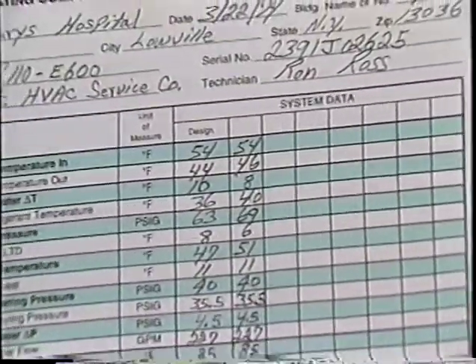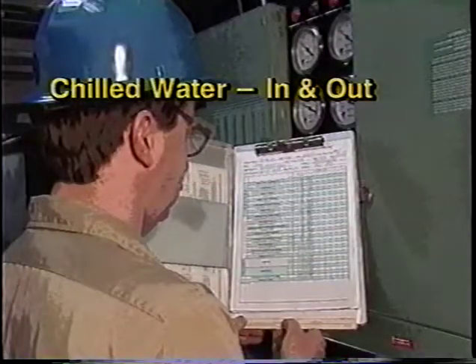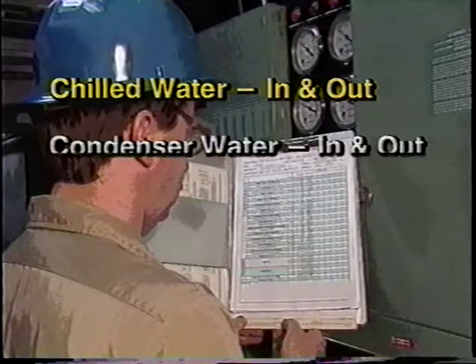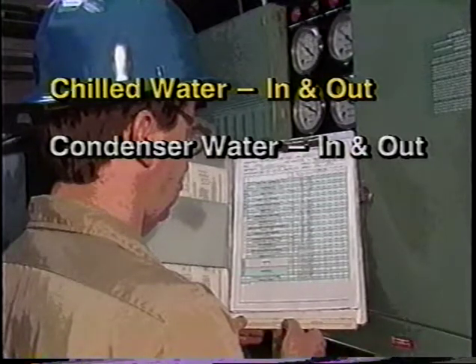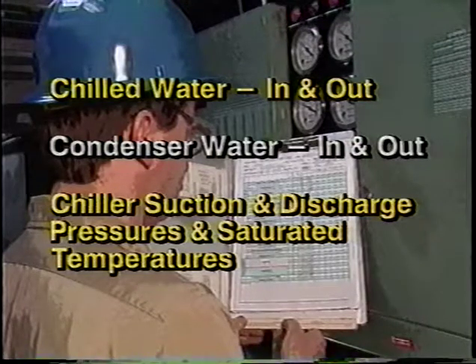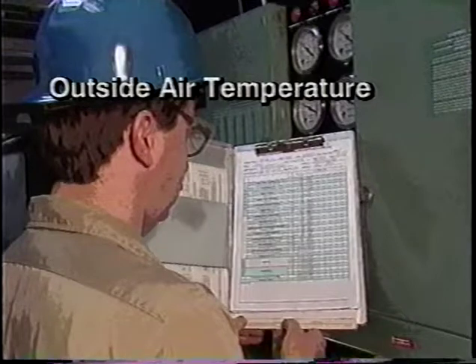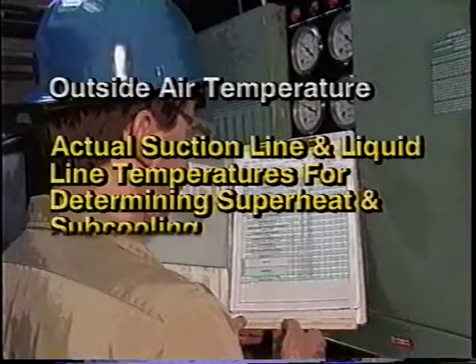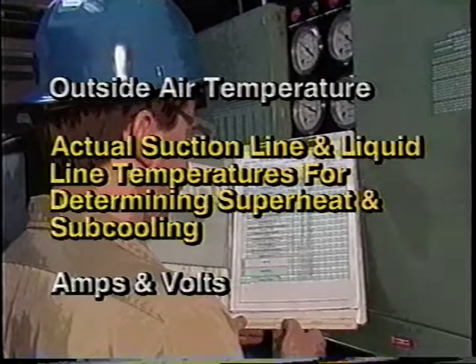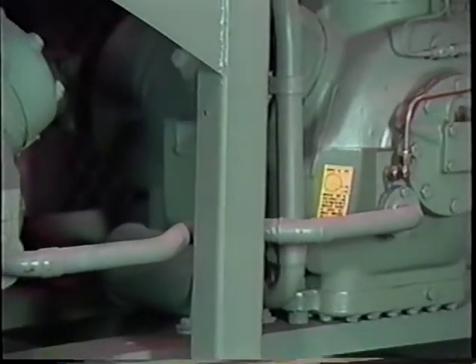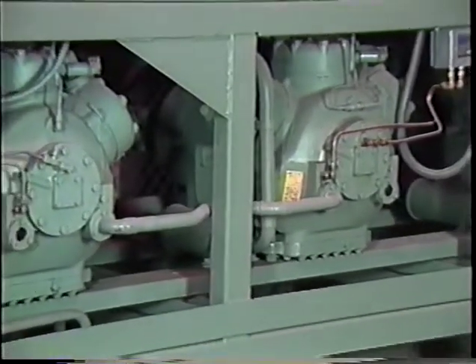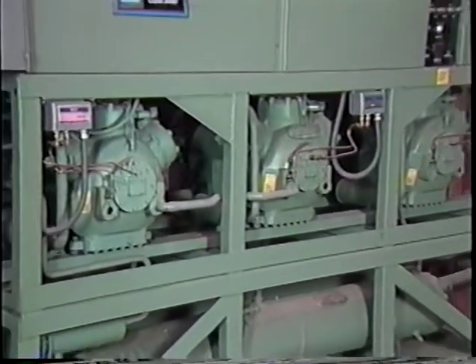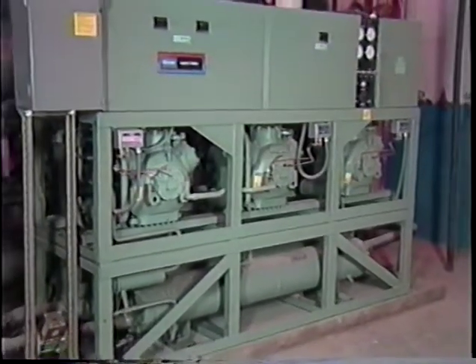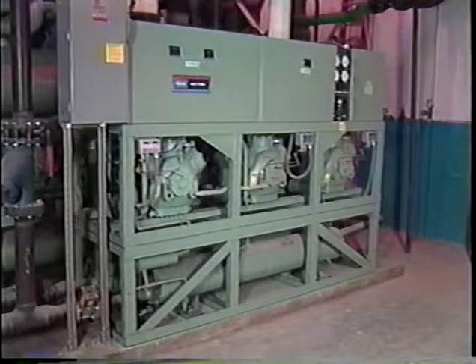You will also need to record the actual operating system temperatures and pressures. For example, chilled water in and out of the cooler, condenser water in and out of the condenser, chiller suction and discharge pressures and temperatures, outside air temperature, suction and liquid line temperatures, and finally, amps and volts. For chillers with 2 refrigerant circuits, a set of data should be taken for each circuit. For the purpose of keeping this program comprehensible and focused, we will treat the chiller as a single circuit machine and will only use one set of data for our troubleshooting analysis.